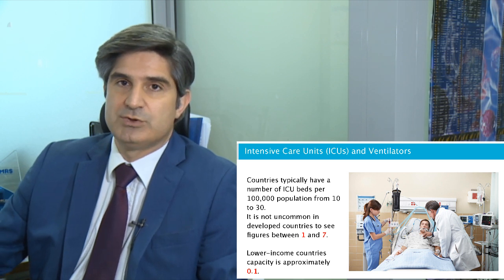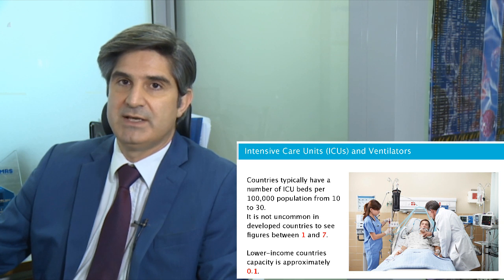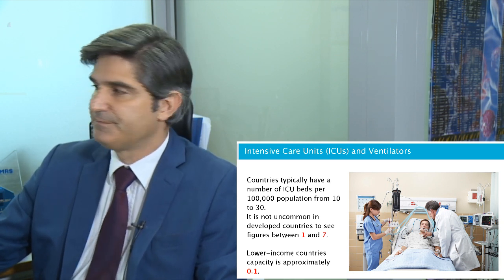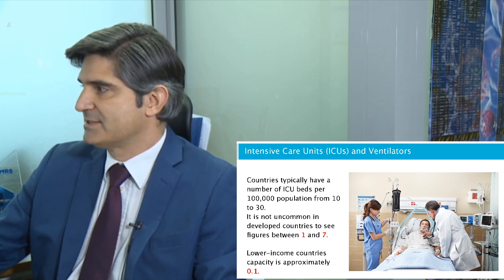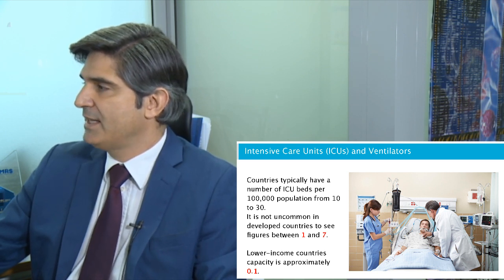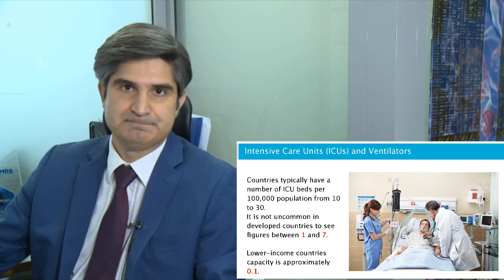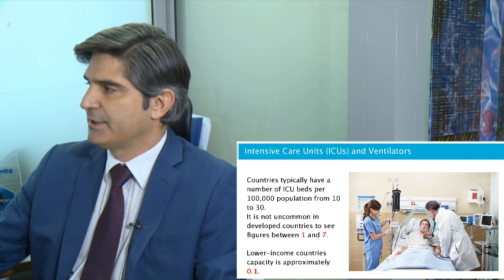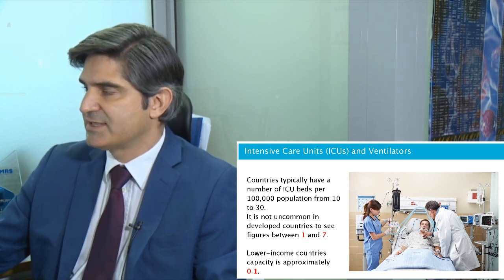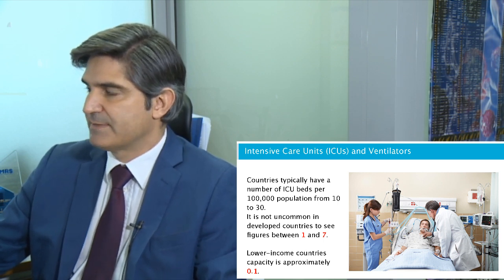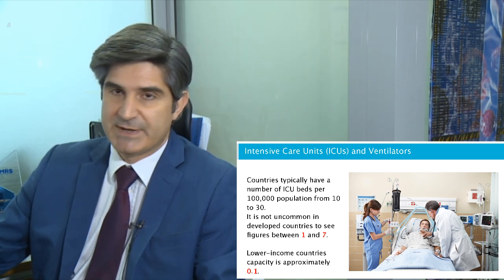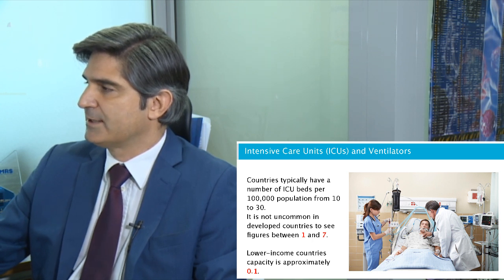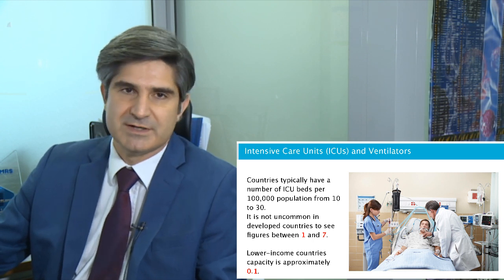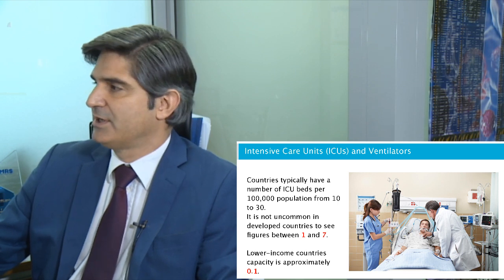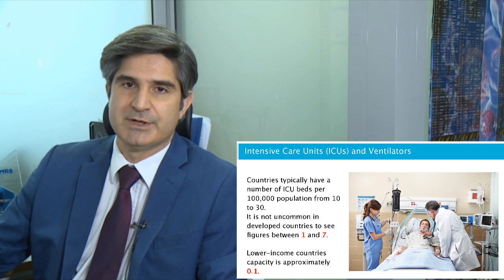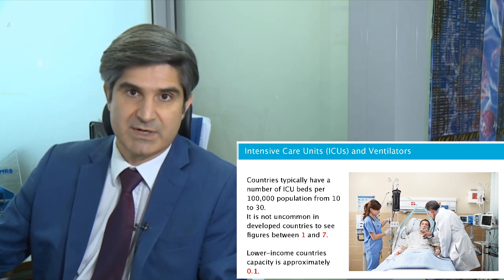So what we are trying to address here is one machine in particular that is available in intensive care units, and this machine is called mechanical ventilator. This is a machine assisting patients in breathing activity. And this machine is typically one per bed. The characteristic of this machine is that it is quite sophisticated equipment that also is a bit expensive, $30,000 to $50,000 typically, and also this machine is produced in reasonable numbers, but for normal situations, right? So in case there is a shortage of this machine, this is where we want to focus our activity. That's where we focused our activity, actually.